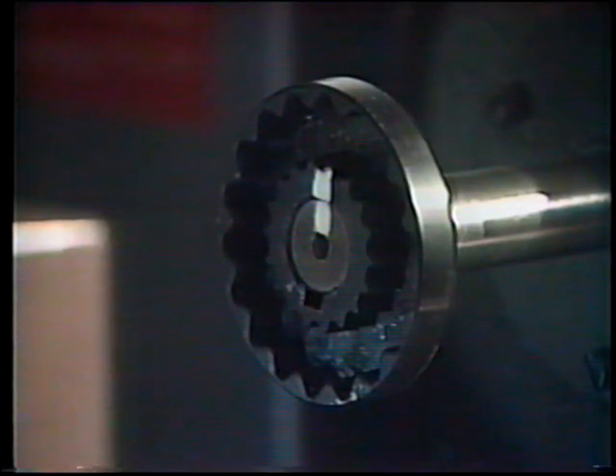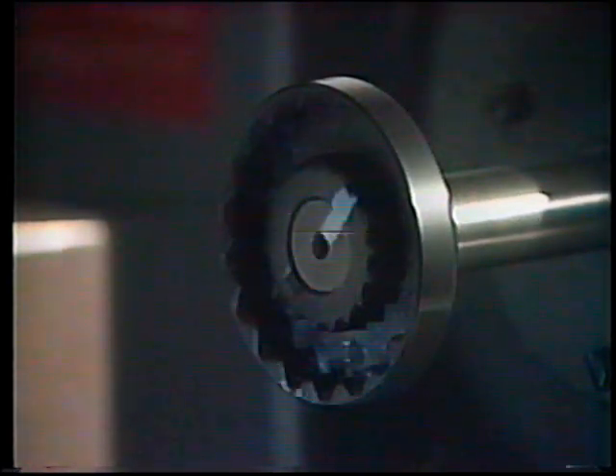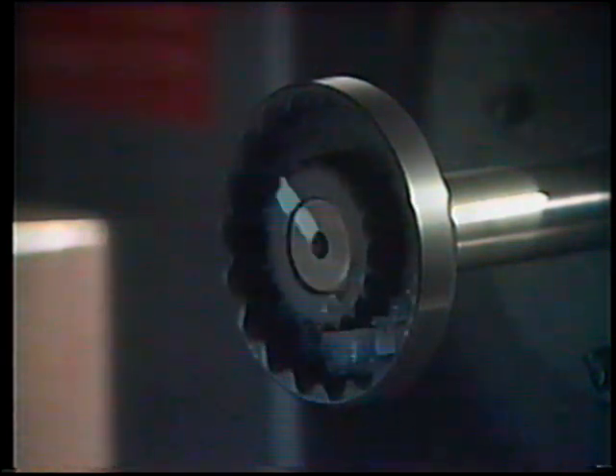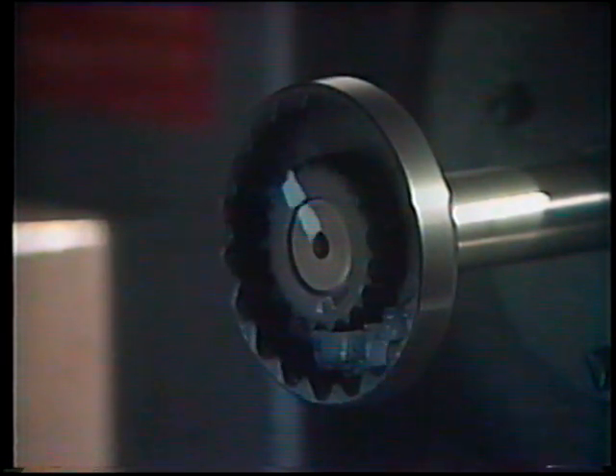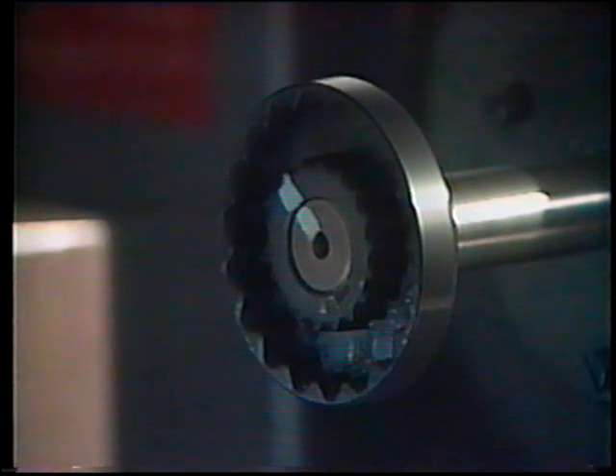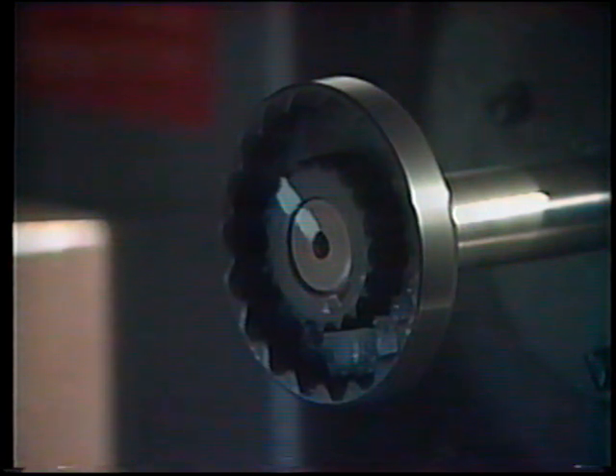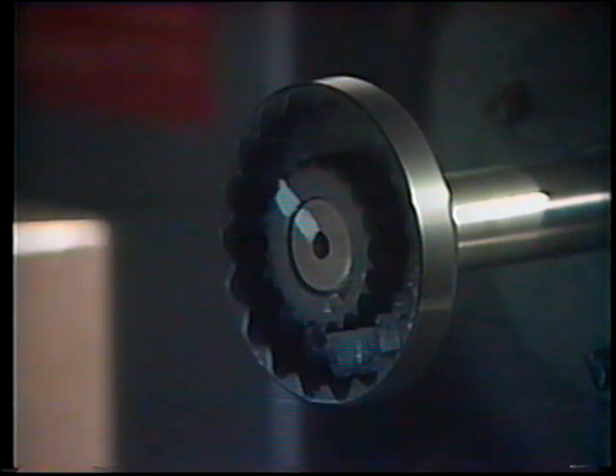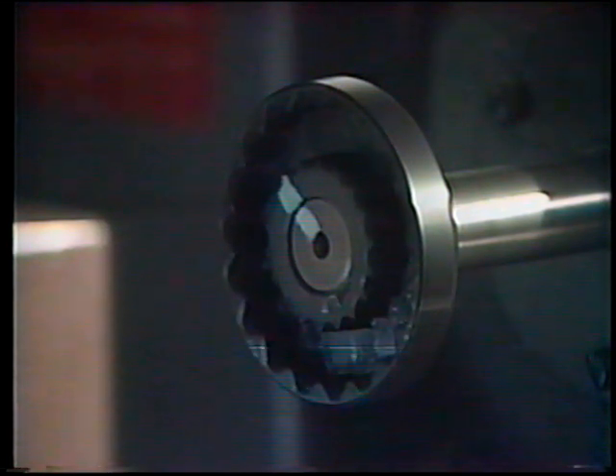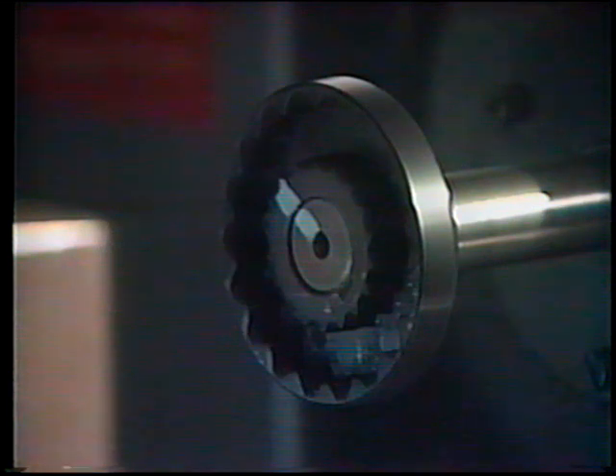The synchronous motor is started. It accelerates by induction and locks into synchronous speed. Notice where the mark appears. Now we'll add load to the motor. Watch the mark very carefully. The mark appears to move backward, but the speed of the stator's field and the rotor haven't changed.